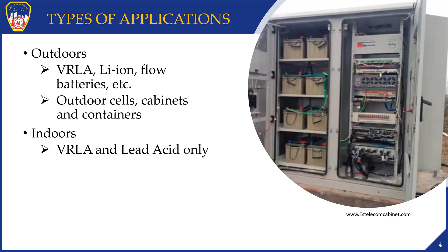There are only two types of installations permitted by FDNY: outdoor and indoor. Outdoor systems can be VRLA, flow batteries, lithium-based batteries, or nickel-based batteries. However, for indoor installations, only valve-regulated lead-acid batteries, VRLA, and lead-acid chemistry-based batteries are allowed.